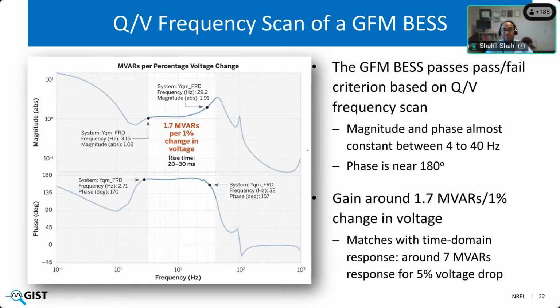So first is Q by V frequency scan. We talked about how Q by V frequency scan should have a more or less constant magnitude within this 4 to 40 hertz. The phase should be closer to 180 degrees. And this is a response. This particular response on the slide is again from one particular vendor supplied black box model of grid forming resource. It shows that the gain is around 1.7 MVARs per 1% change in the voltage. And this correlates very well to the response we see in the time domain. Like this gain has a direct correlation with the voltage jump response.